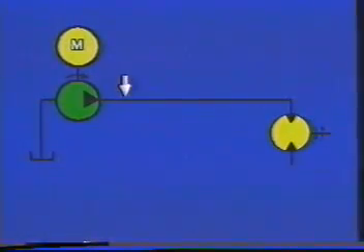Since it's a positive displacement unit, if it were to stall, it would not accept any more oil. The pump, also positive displacement, would stall too, since its outlet would be blocked. This, in turn, would stall our electric motor. Oh, you say, wait a minute. Let's put a relief valve in this line.